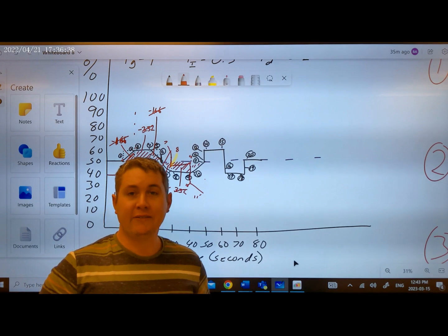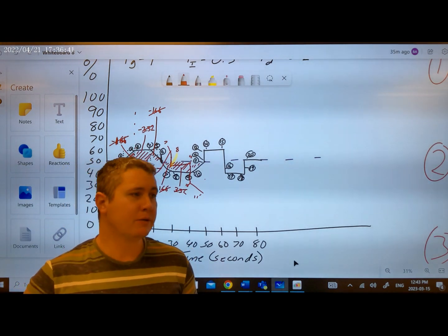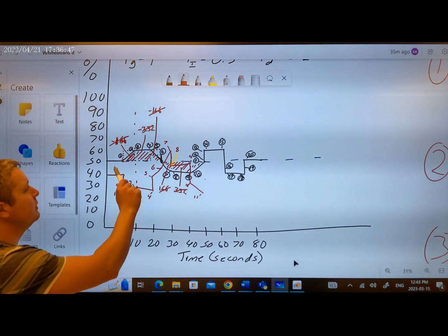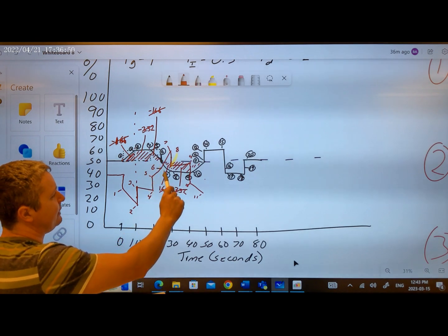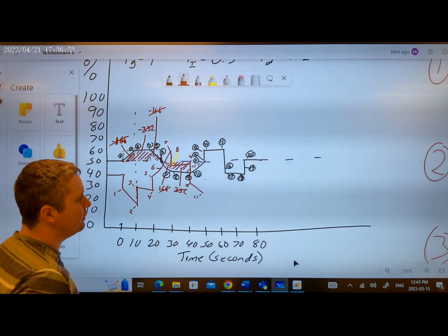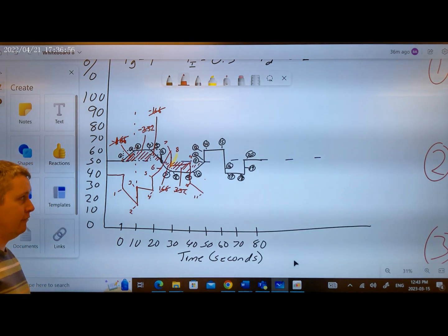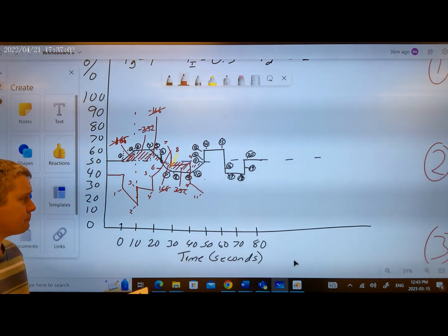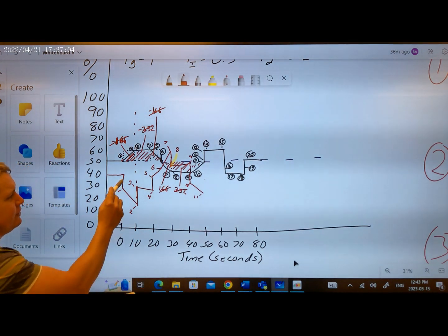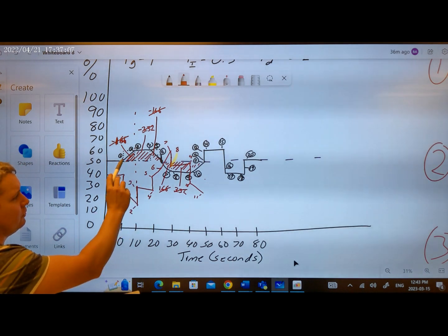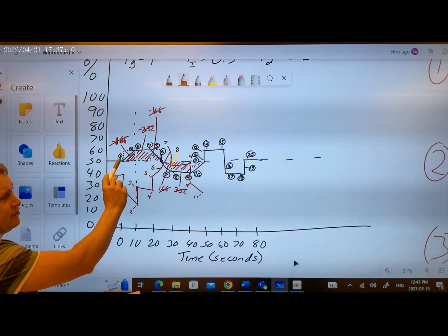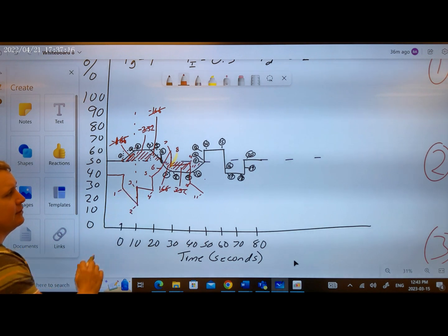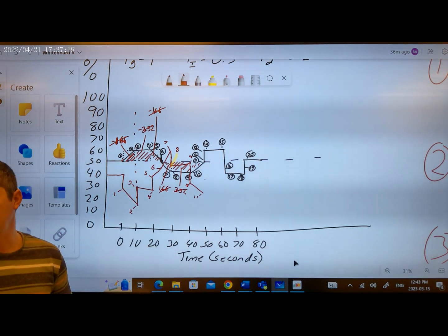So we have essentially looked at what would happen to a controller output when the process variable goes above the set point and then below the set point, not in a digital or square wave format, but it has a bit of a ramp. Now, notice that the output did not just follow the reverse action of the process variable, but yet it almost looks like there's spikes. Okay, that's because of the derivative function that was happening.